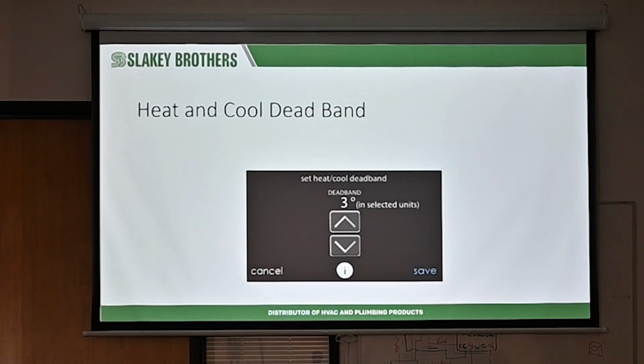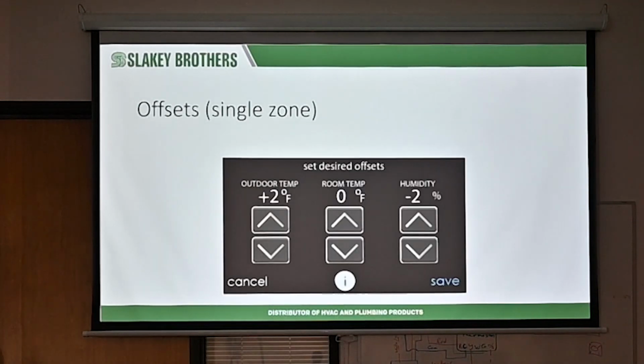Heat, cool, deadband. Okay, that's if I want heat at this point, cooling at this point. What's the closest temperature you can have it? You can do as little as 1 degree between the two. But be careful, too close together, heat and cool could conflict. So that's why they show like a 3-degree deadband in between the heat and cooling set point for auto.